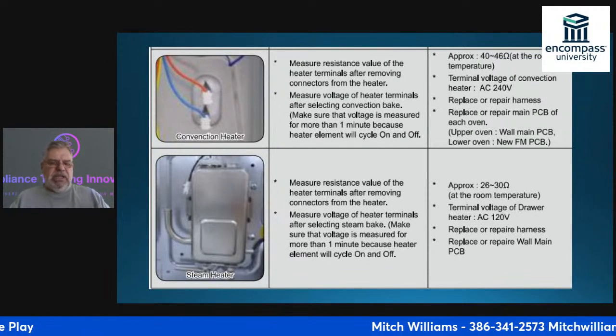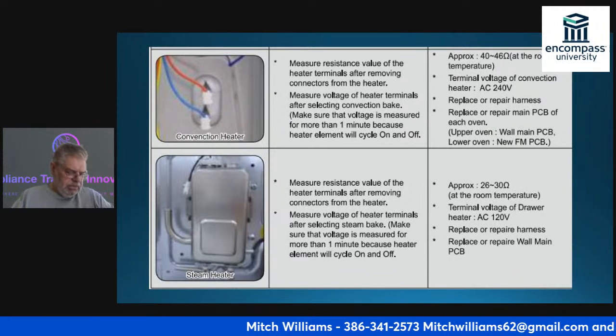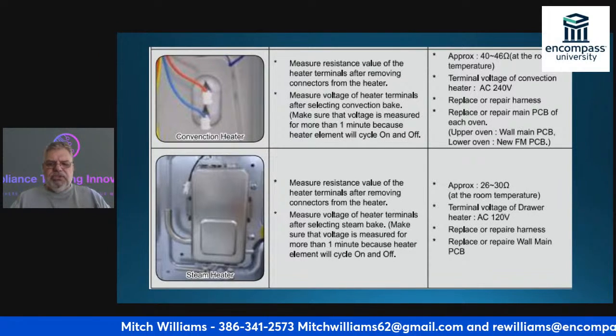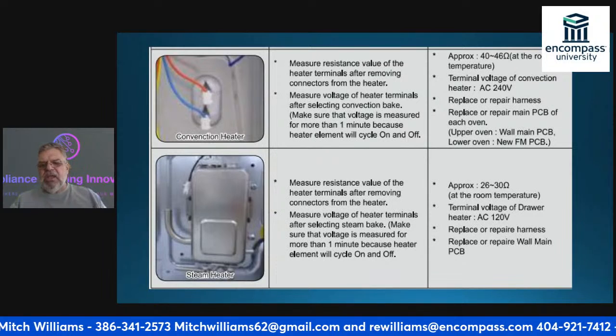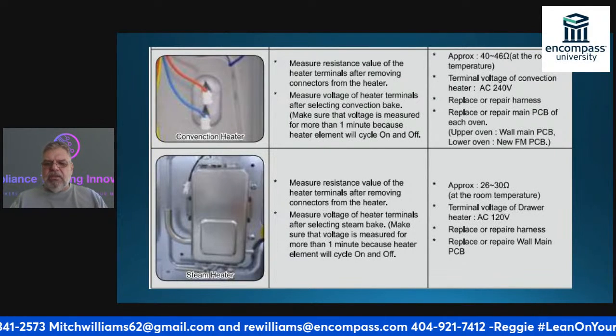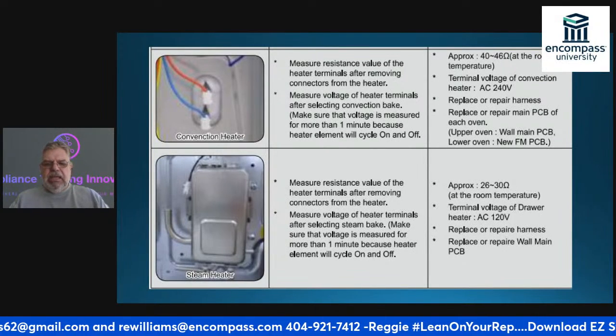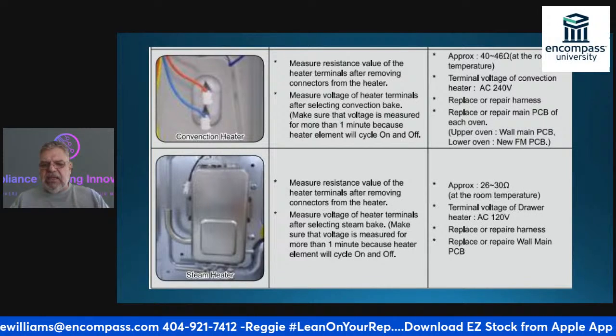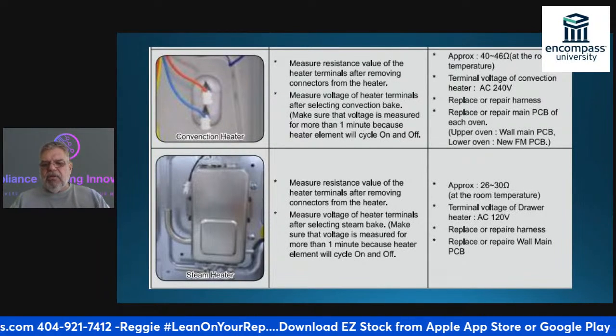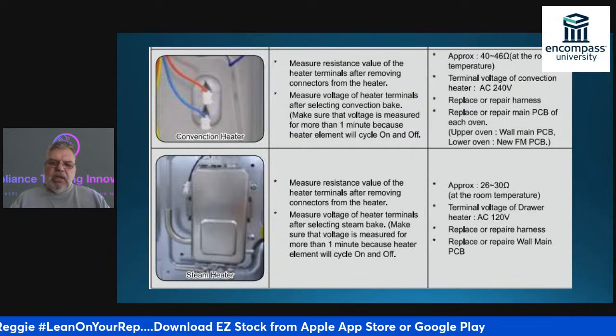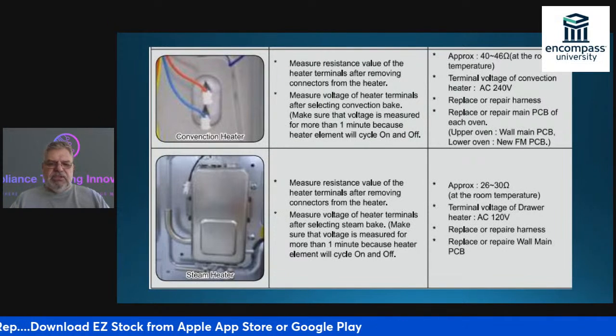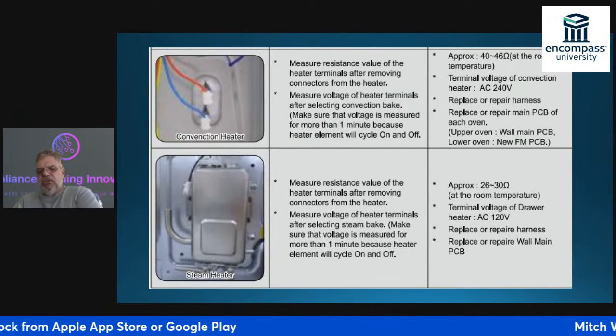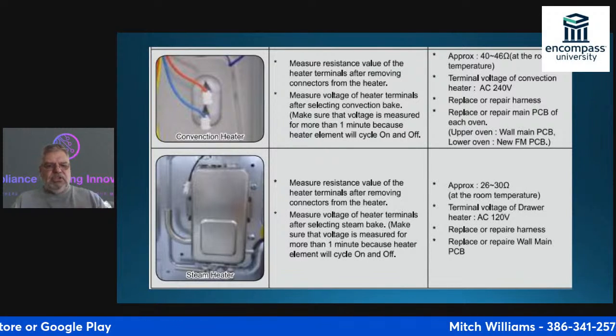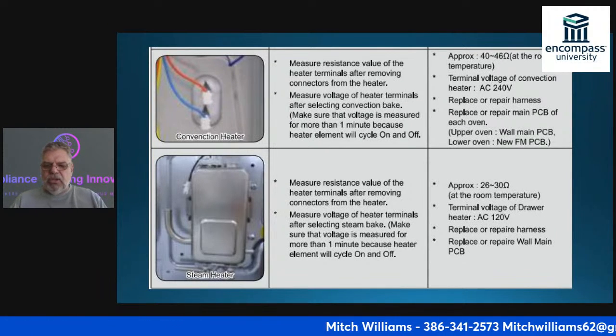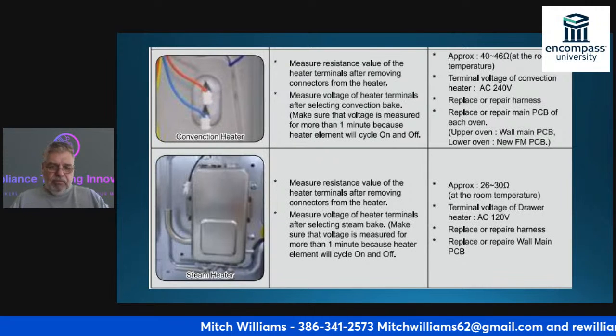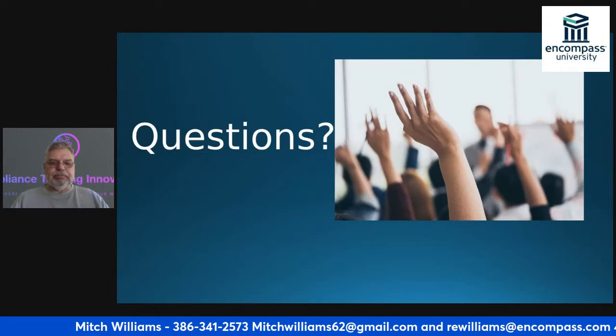So for our steam heater, how do I replace it? I measure the resistance at the heater terminals — I should have between 26 and 30 ohms. Then I can plug it all back together and flip the switch. The terminal voltage of the drawer heater is 120 volts. If I don't have voltage coming through the wire, I check the wire to make sure it's good. If the wires are good, I'll have to replace the main PCB.